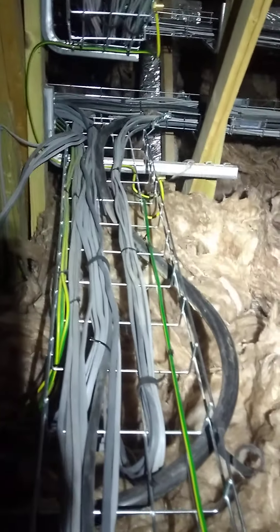The big black one that you see snaking through there is the main feed distribution board. And then you can see runs coming up the back here, popping through, that feeds into our distribution board. It's good to have our cables up and off the insulation because that helps to keep them running cooler than they would otherwise do.